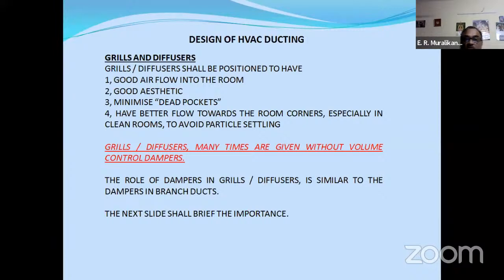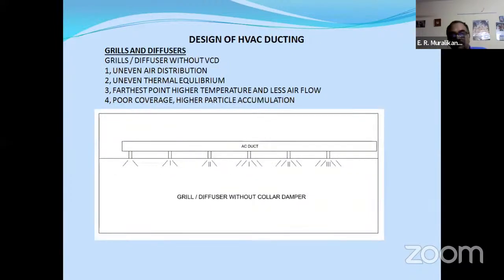Now, grills and diffusers shall be positioned to have good airflow into the room, good aesthetics, minimize dead pockets, and have better flow towards the room corners, especially in clean rooms, to avoid particle settling. Again, many people do not give volume control dampers in the grills and diffusers. The role of the damper in a grill or diffuser is similar to that in the branch duct. I'll just show you how important it is. Now, grill diffuser without VCD: uneven air distribution. Is this picture clear, all of you? This first grill is getting a good quantity of air, and the last grill is having very little air.